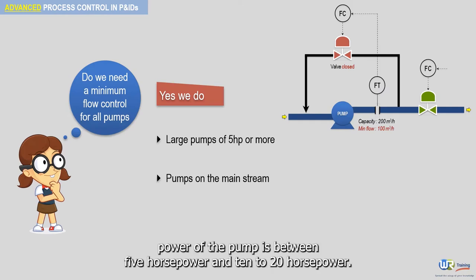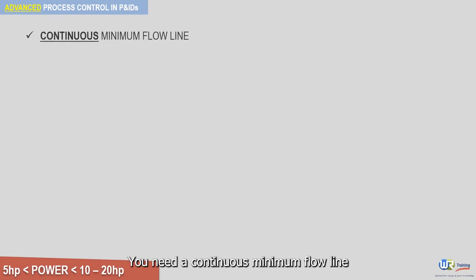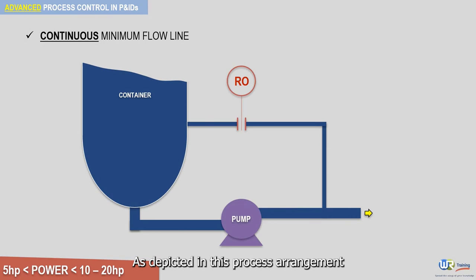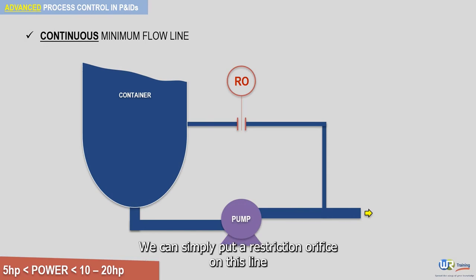When the power of the pump is between 5 horsepower and 10 to 20 horsepower, you need a continuous minimum flow line. As depicted in this process arrangement, instead of going to the expense of installing a control valve, we can simply put a restriction orifice on this line.